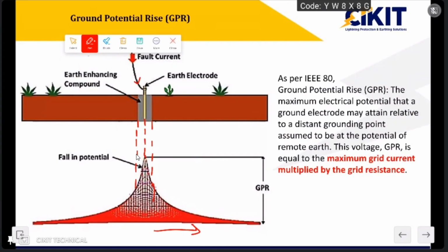If you closely observe this, most of the potential is dropped in an area very near to this earth electrode. That is the reason we provide earth enhancing compounds surrounding the earth electrode, because most of the potential will be dropped in an area very near to it. If I provide a highly conductive medium in that particular area, the performance of the earthing can be improved. So that is the reason we provide earth enhancing compounds in the area surrounding this earth electrode.